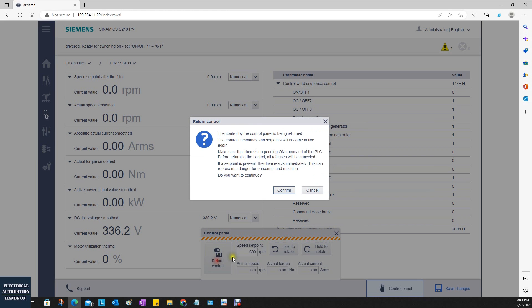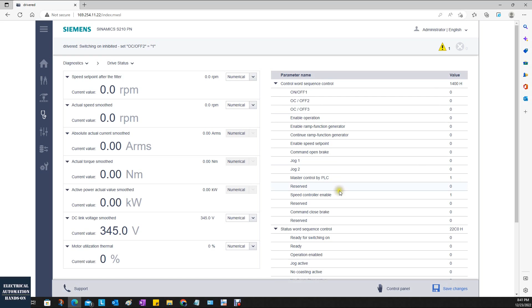Okay. And if I'm using the controller, from here I will stop it. From here, you will see the status word and the control word. This depends on the telegram you are using. The typical Siemens telegram, for example, the 105, this is a typical servo control telegram, or the telegram 3. They include the control word and the status words. Then let's go to the communication.